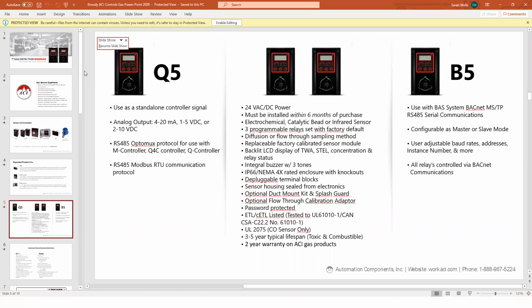As far as power on these systems, I'm going to let Dave talk about 24 AC versus DC, and what we recommend. So 24 AC can be used with the M controller and the Q5s. We prefer using DC power. All these devices, the Q5 and the M controller, are full wave rectified, so we don't recommend sharing transformers. If you're going to use AC, we recommend a dedicated transformer for powering everything. If you can, DC power is a lot easier to work with and a lot less troublesome when it comes to wiring.